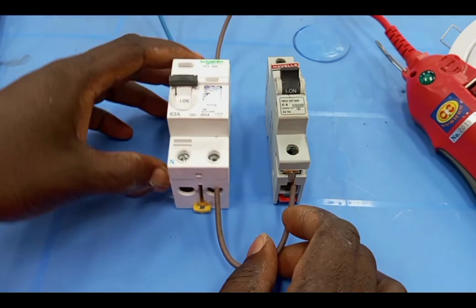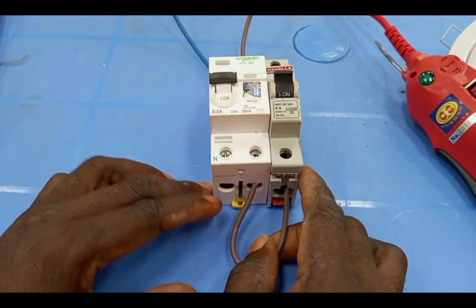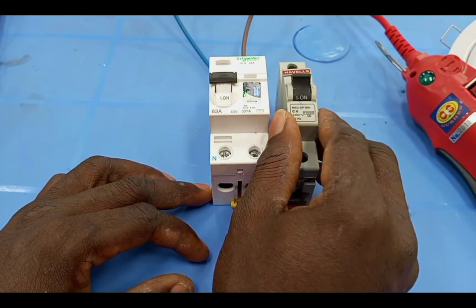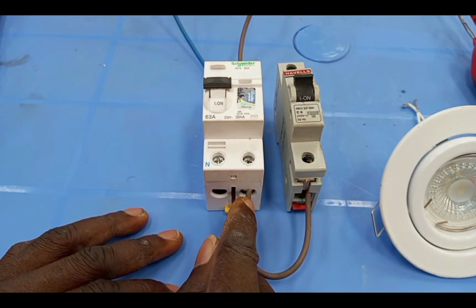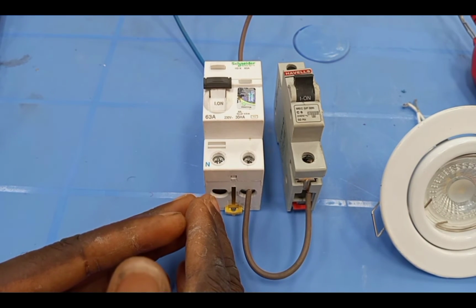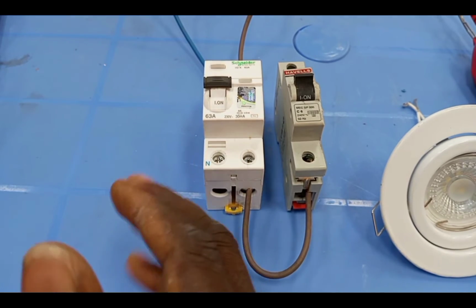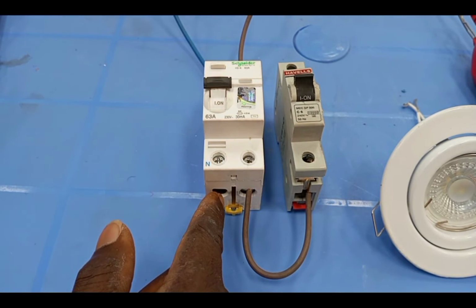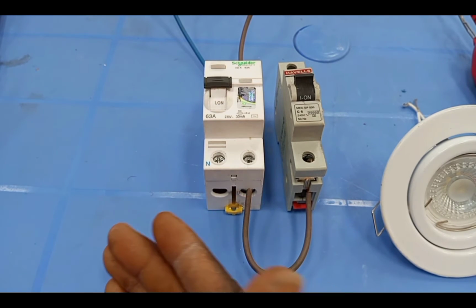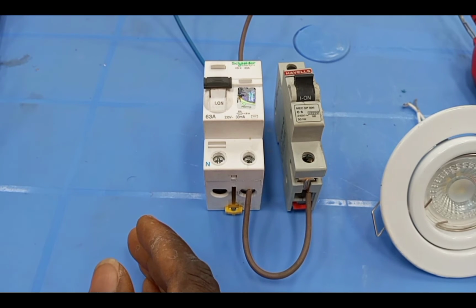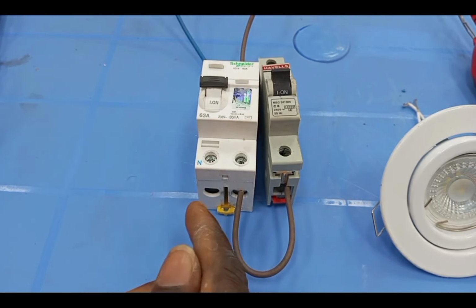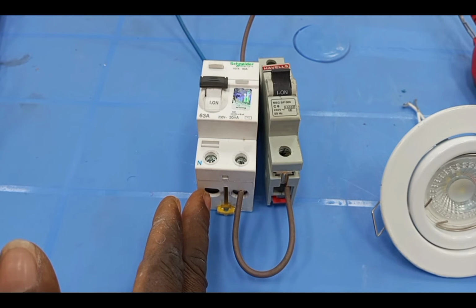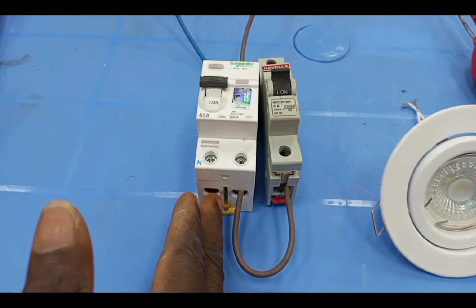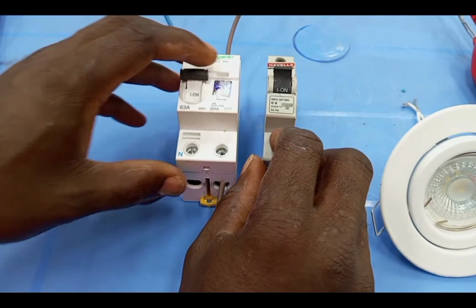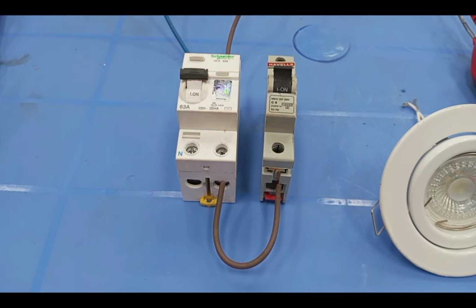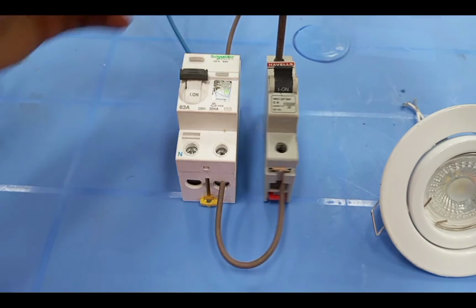So now the live input to the miniature circuit breaker that is protecting the particular circuit, in this case my lighting circuit, is taken from the output of the RCCB. Now in the case where you are using one RCCB to protect the whole wiring, you can connect the neutral output to the neutral bar in the consumer unit. But in the case where you are using it to protect only some particular circuits, then you have to connect the neutral to all those circuits from this same terminal. All right, so look at how it works. So here, my live to the lamp will be taken from the output of this miniature circuit breaker.